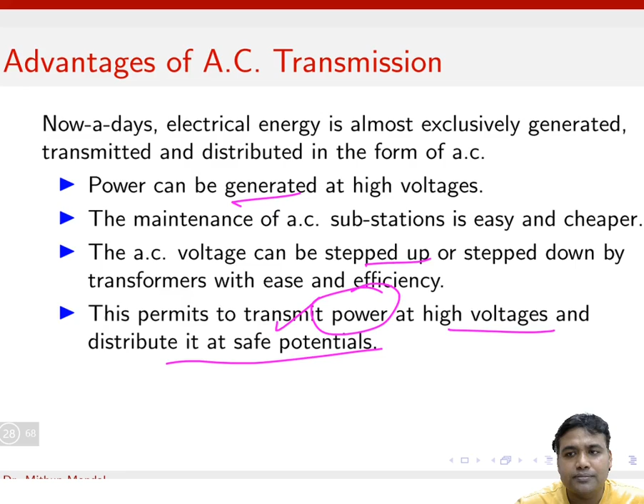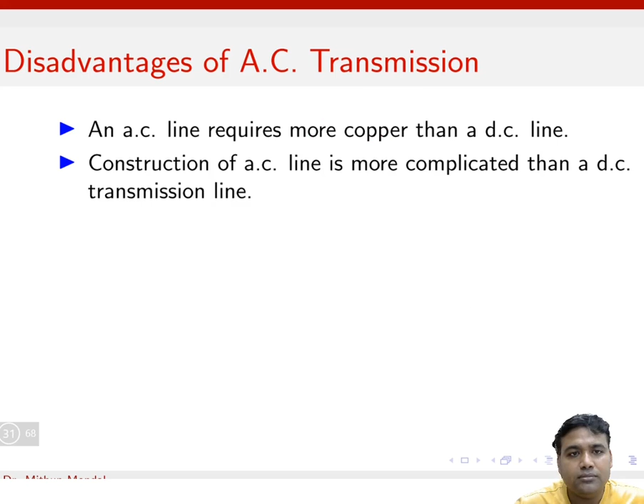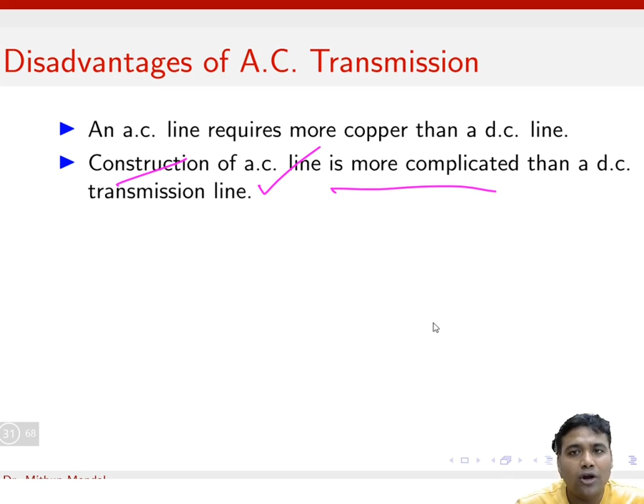AC lines require more copper, because we have already seen that in AC lines you require 3 conductors, whereas in DC lines you require 2 conductors. Construction of an AC line is also more complicated than a DC transmission line, because it involves transformers and other apparatus that are not present in a DC transmission line. And due to the skin effect, which we have already discussed, the resistance of the line will increase, due to which more losses will take place in AC transmission.